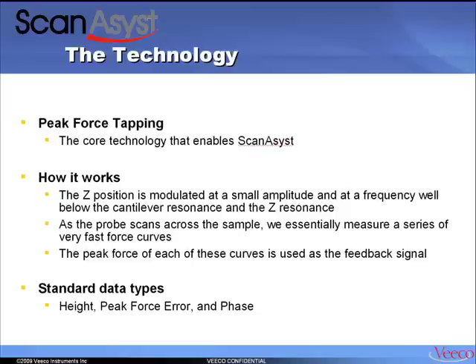That brings us to the data types that we can achieve. We get a height or height sensor signal, depending on whether you have a system with a closed-loop sensor. You get an error signal — the peak force error in this case. And every time you have modulating signals, you can also measure some kind of phase signal. It should be mentioned that the phase you measure in peak force tapping is not exactly the phase you measure in tapping mode, and it's questionable whether it will ever be completely clear what the phase in tapping mode actually is, except being a high-resolution qualitative signal.